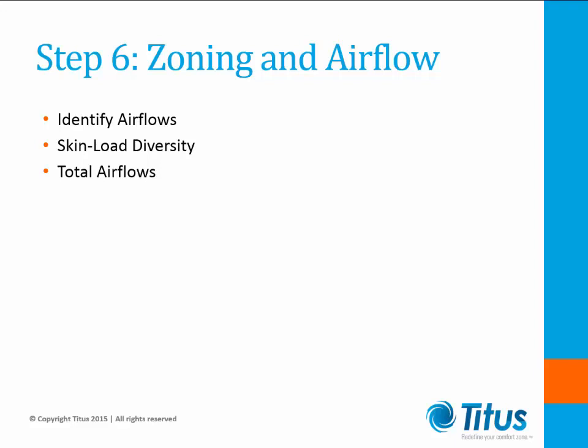Skin diversity can be determined by reviewing the system peak versus the sum of the peaks reports or similar reports from your load program. After diversity is calculated and accounted for, the airflows are totaled back to the air handling units.